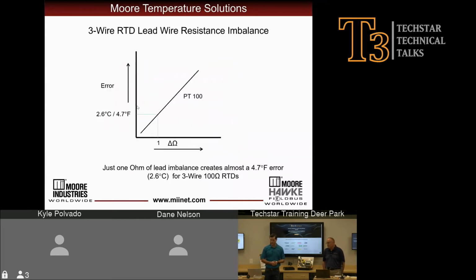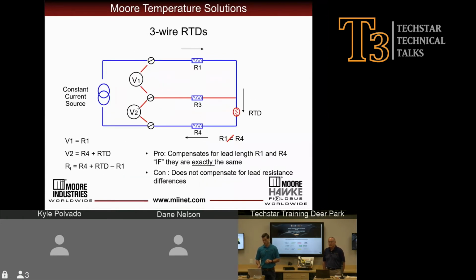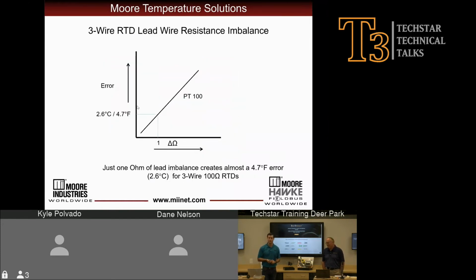Now, shown here, I just have a short chart that I wanted to go over to let you know that if we have just 1 ohm of imbalance, that results in almost 4.7 degrees Fahrenheit of error. So just 1 ohm of difference between R1 up here, the resistance in this lead wire leg that we're measuring, and the resistance in this lead wire here that we're not measuring and that we're actually guessing at. Just 1 ohm results in 4.7 degrees Fahrenheit of error. So that adds up pretty quick if there's more corrosion on one wire than the other, or if we're having some type of problem guessing what that R4 leg might contain in terms of resistance.